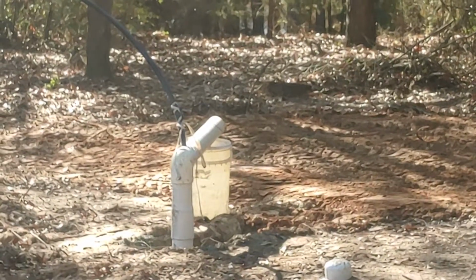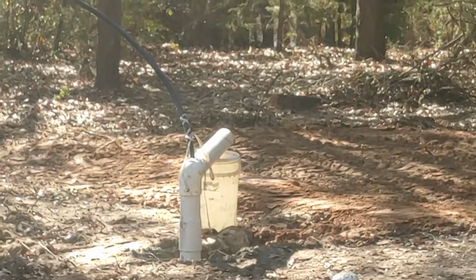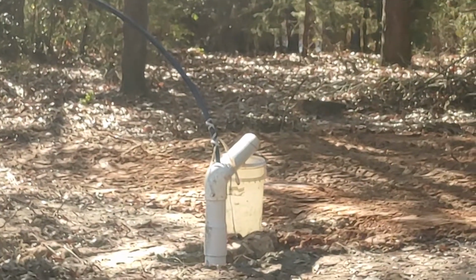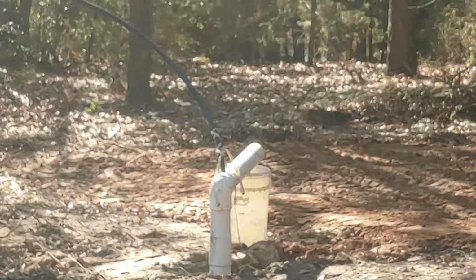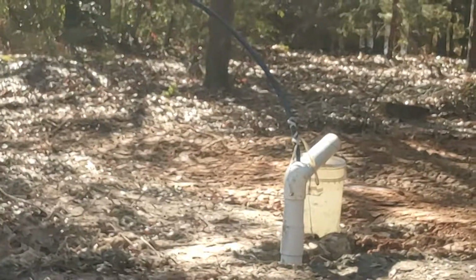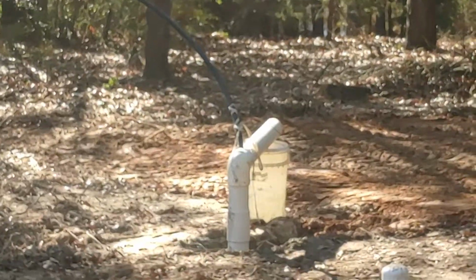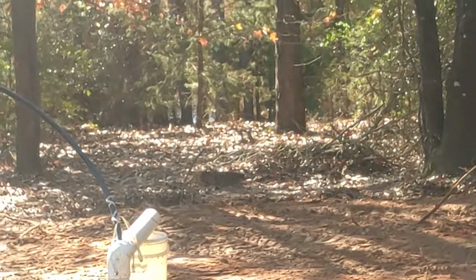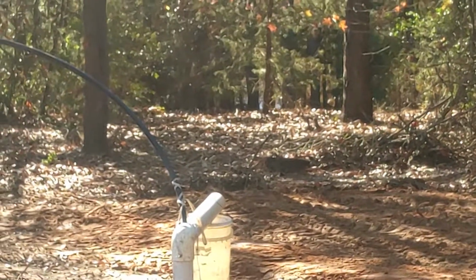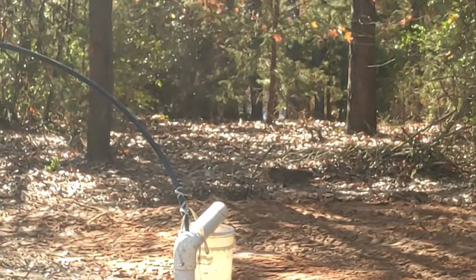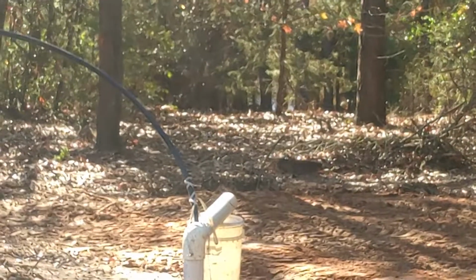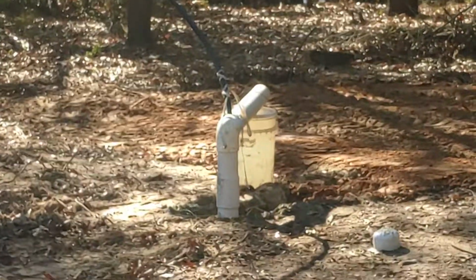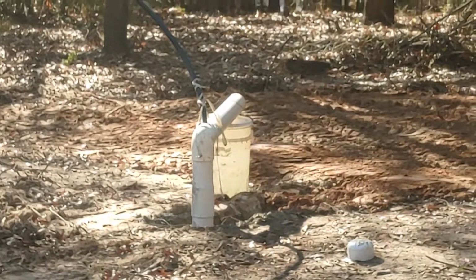And so that's the thing. The higher the water, the better your well is. You have a higher drawdown availability, and it'll draw it down. So when you start pumping, it's going to get to the point where the water can bring in the same time and equal out the head pressure. It's got several factors, but the head pressure and what the screens can handle, the sands can handle, and the well produces. The way water moves in is a differential in head pressure. Like right now, whatever that comes up to, we can calculate from how much water you got and tell you what the head pressure is in that formation. You don't need to know, but if you wanted to, you could, because that's where it comes from. So when you start pulling it down, you got a differential in head, so it starts getting that water moving, and that's what we're doing right now.